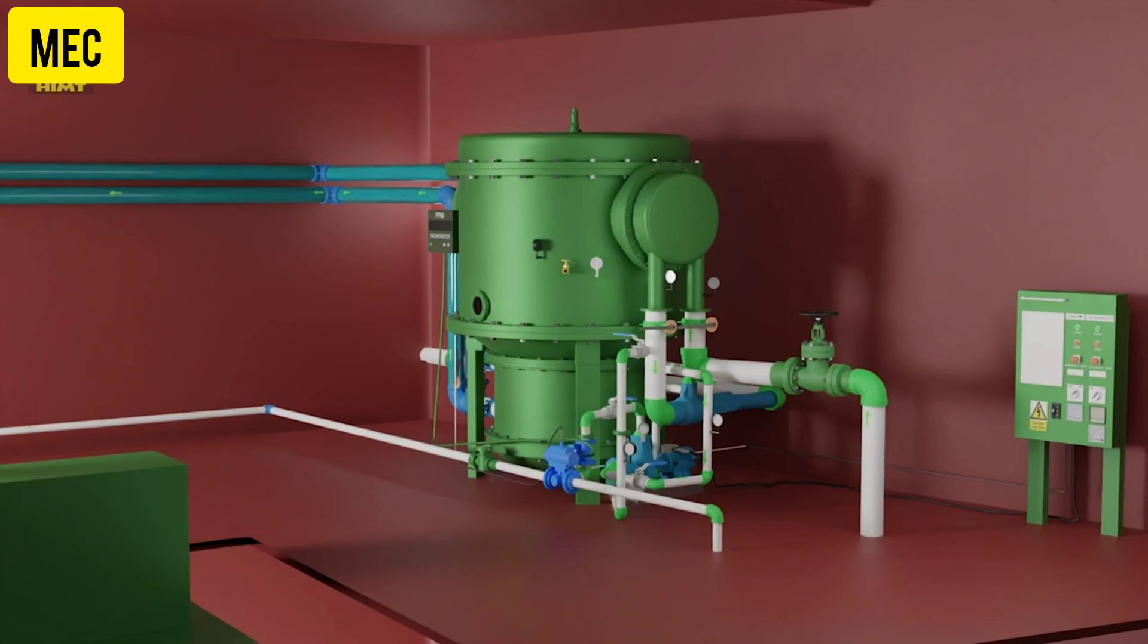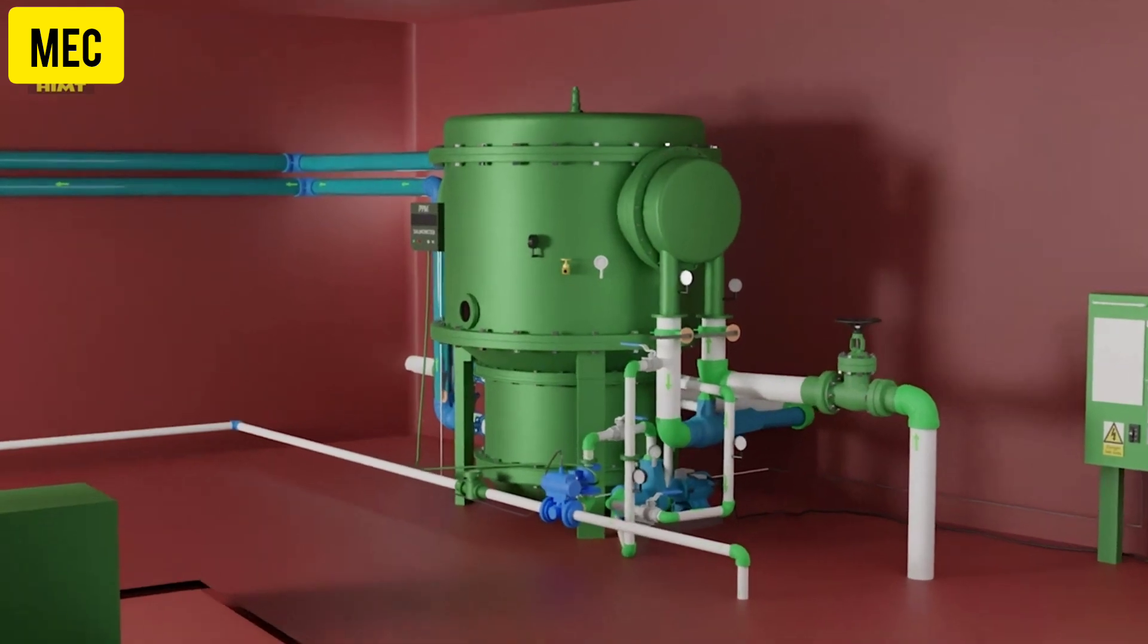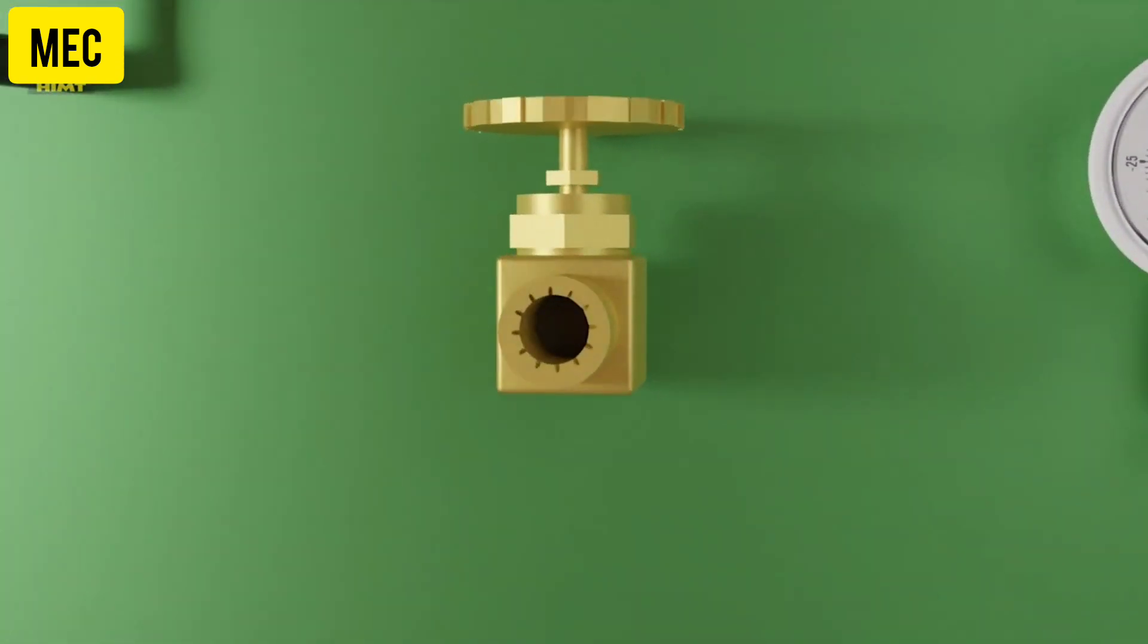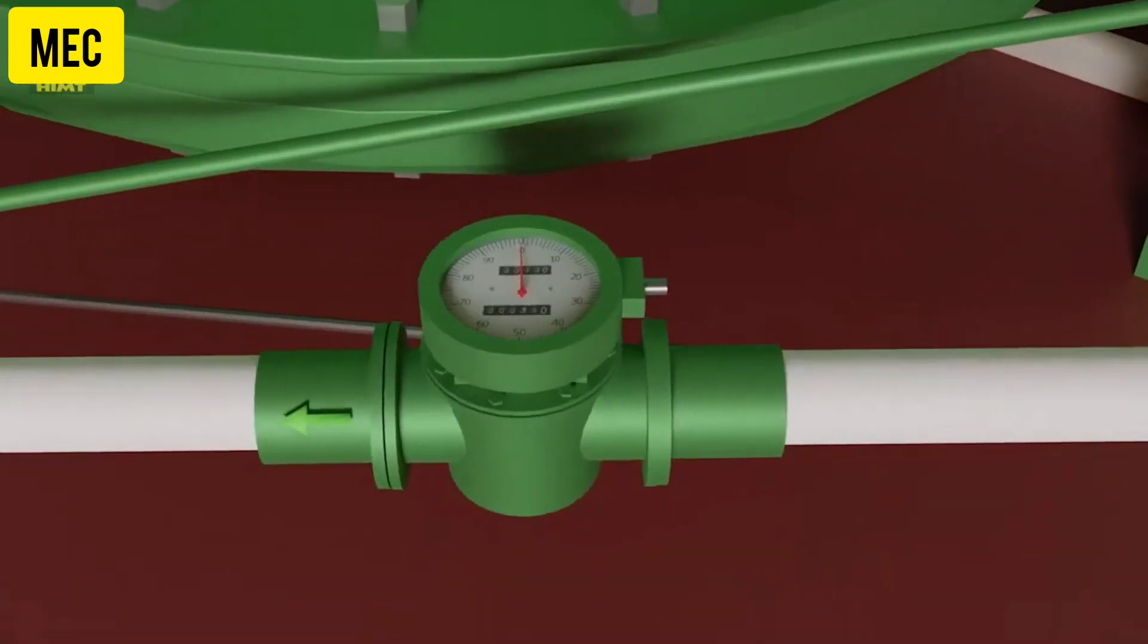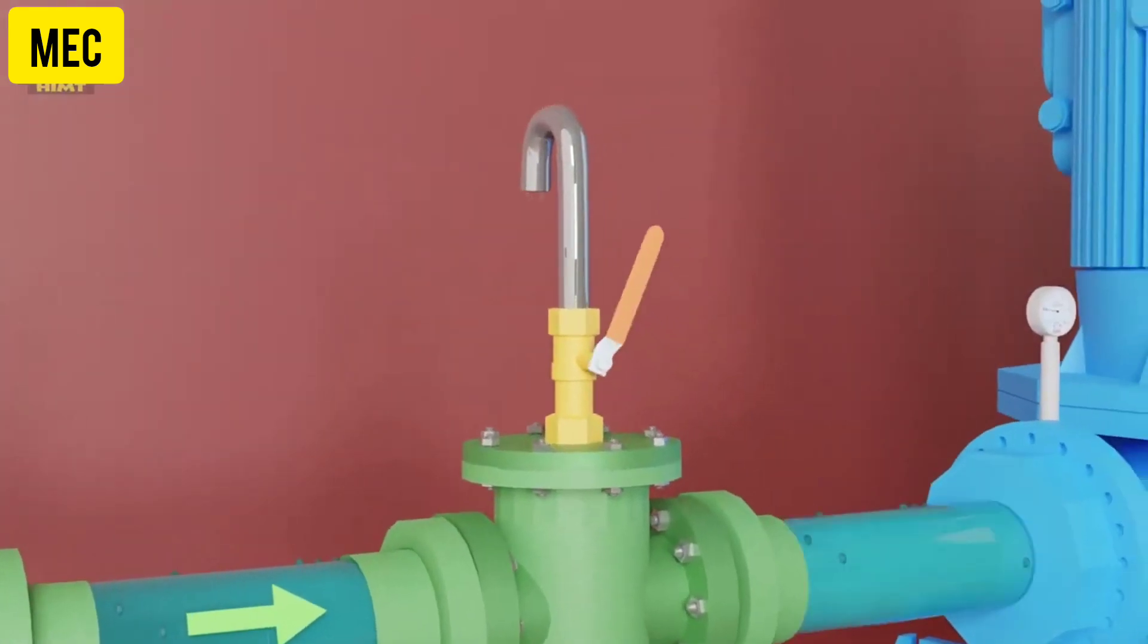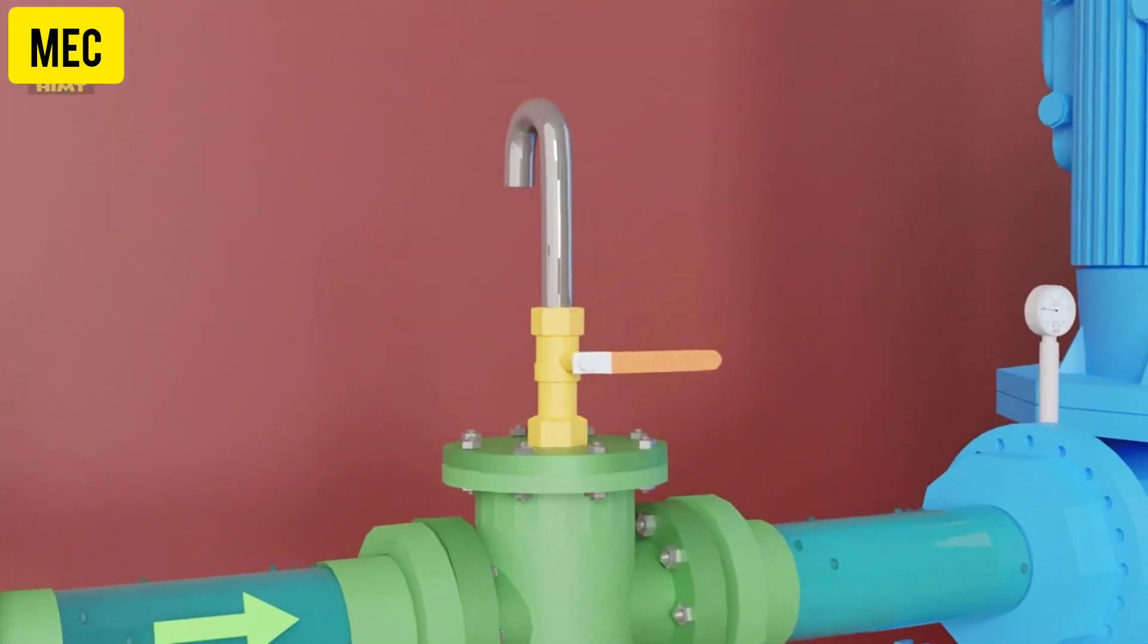Now let's see the step-by-step operation of a freshwater generator. Let's dive in. Let's begin by shutting the vacuum breaker valve and take note of the flow meter reading. Now open the suction side valves of the ejector pump and purge the air from the system using the vent valve on the strainer.